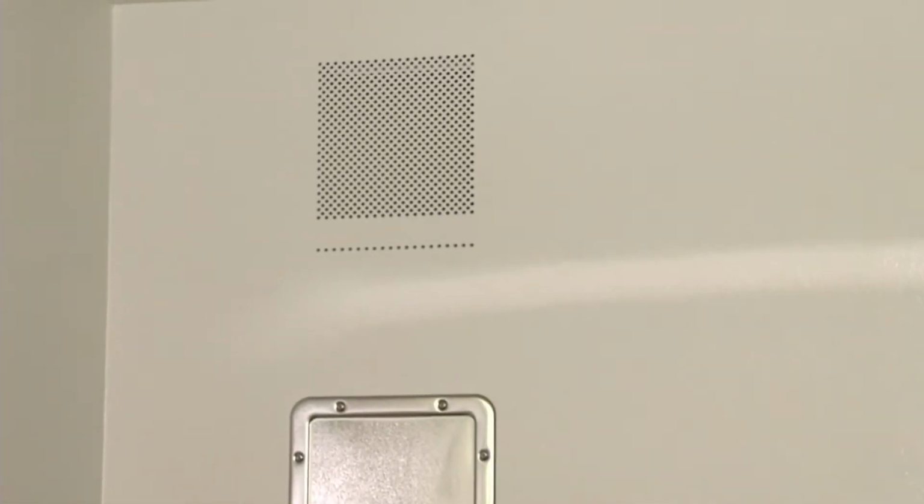And the rear chase itself helps answer a question: how can we get a negative pressure cell? How can we direct the airflow so that we're not spreading any virus or bacteria, airborne, anything through the facility? And we're able to do that because we have an exhaust in the rear part of the cell, route it to the chase to an appropriate HVAC system, and we're not then pumping that air by the design of the cell back around the common areas for the inmates.